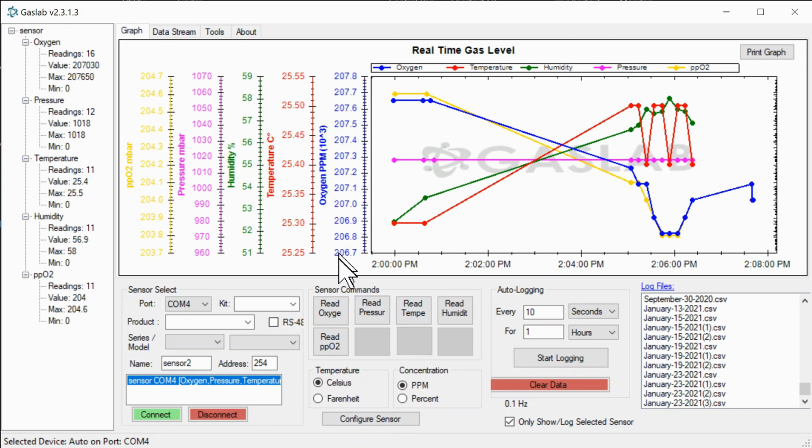So you see this is given to you as partial pressure. And if you want that converted, you can get it into percentage concentration. So if you're doing it medical, you really want to have partial pressure, which is always available. But the concentration that we display close to it, we give you the abilities for the annotation, so that some people want Fahrenheit, some people want centigrade. So that's handled here as well.